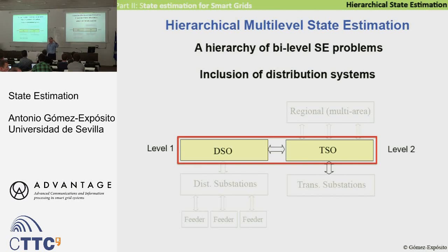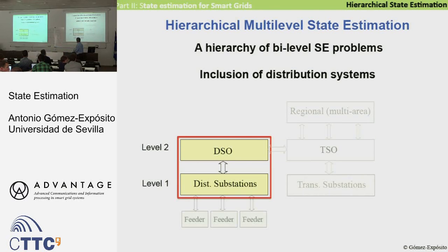Yeah, this hierarchy correlates with the voltage, of course. Distribution level depends on the country. In Spain, for instance, up to 132 and 30 kV is called distribution, even though it is not radial, it's mesh. Technically it should be called subtransmission, but regulatorily it's called distribution—it's a mistake, but anyway. Transmission in Europe is 230 and 400 kV, and feeder can be medium voltage and low voltage. So this correlates with, and is in accordance with, the physical and logical structure of the network.